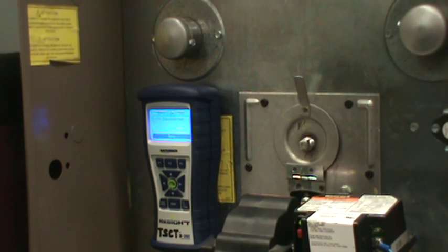Okay, what we're going to do now is measure the overfire draft on an oil-fired unit. This happens to be a furnace. It's a Category 1 venting system, but most of your furnaces, gas or oil, are going to be firing in a negative combustion area, mainly for safety. If you have a cracked heat exchanger, you're not going to have carbon monoxide going out. You'll have air coming in, which we'll talk about using combustion analyzers to determine cracks later on.